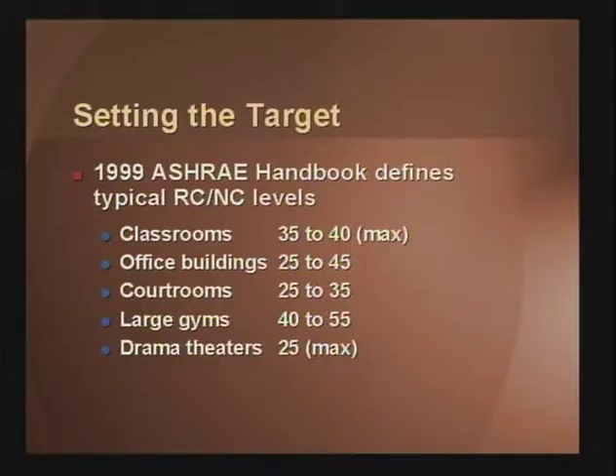If all that's in the budget is basically window units, you don't have a lot of dollars available to acoustically optimize the system. What does ASHRAE recommend for the spaces? Well, here are some sample application sound targets. In the 1999 ASHRAE handbook, it defines RC targets for these different applications. Now, previously, we were using NC levels, and they still apply. NC and RC are about the same, at least in the 500-1,000 hertz octave bands. RC addresses the extremely low frequencies, 31 hertz, 16 hertz.